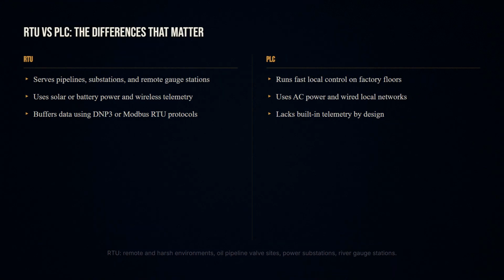RTU: remote and harsh environments, oil pipeline valve sites, power substations, river gauge stations. Power comes from solar panels or batteries. RTU communication is wireless: radio, cellular, satellite. Two telemetry protocols handle most RTU deployments globally: DNP3 in electric utilities and water, and Modbus RTU elsewhere. Built-in data buffering handles link outages. PLC: factory floor, AC power, wired local network, fast local control, no built-in telemetry. The boundary is blurring as some PLCs add cellular modems, but the design intent stays distinct.